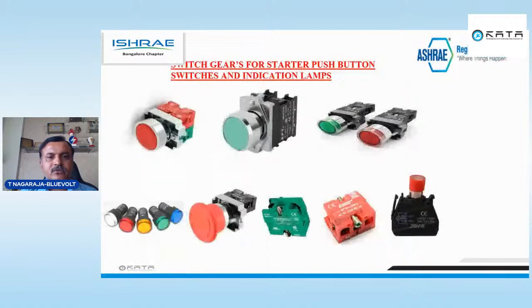These are the symbols for contact and overload. Then for switching on, switching off and indication purpose, we have to use push buttons. I have given various push buttons just for you to know. For indication I have given red, yellow, blue, green, white. RYB: red indication for one phase, yellow for another phase, then blue for the third phase, that means R phase, Y phase, and B phase. Then green for running and red for off in push buttons. Whereas in indication, it will be reverse. When it is the green indication, it is safe. When it is the red indication, it is danger.